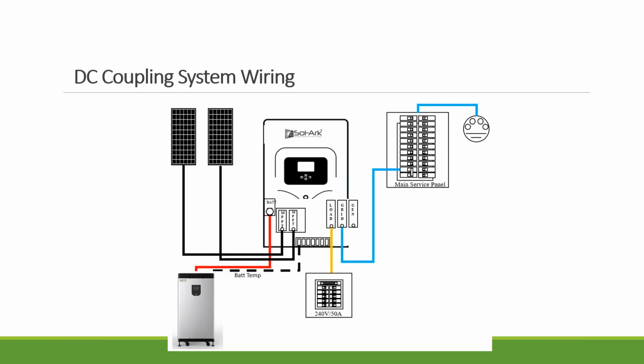Here's the DC coupled system. Let me show you the wiring to explain. Solar comes in to 2 MPPTs, and each MPPT has 2 strings. Then you have the battery here, while the charge controller sits here. The PV comes in and charges the battery. Then you have a load, the 50 amp essential load panel, connected to it. You can connect to the grid, to the main panel and then to the grid. You can also use a generator as an option, hooking up to a generator.